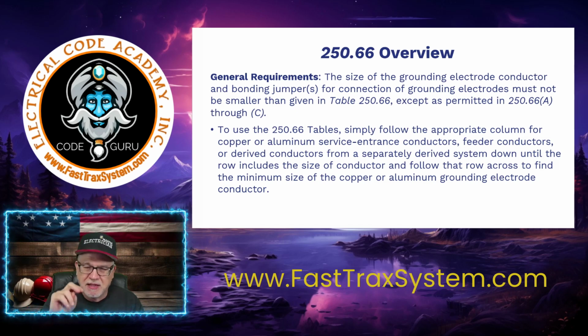So you have an A, a B, and a C. And we're going to look at those today, and that's pretty much the main topic of this brief video for you. Now, to use 250.66 table, simply follow the appropriate column for copper or aluminum service entrance conductors, feeder conductors, or derived conductors from separately derived systems, like a transformer is an example of a separately derived system, down until the row includes the size of conductor, and follow that row across to find the minimum size of the copper or aluminum grounding electrode conductor. That sounds simple, doesn't it?